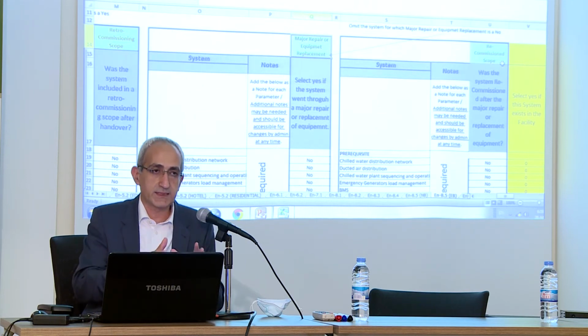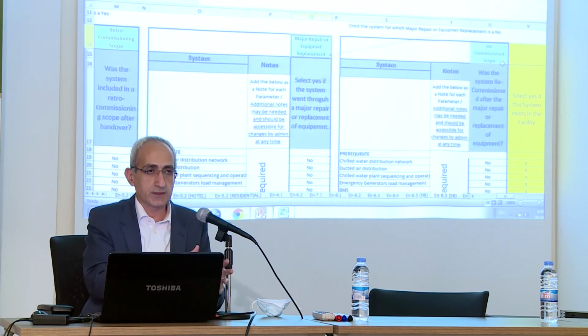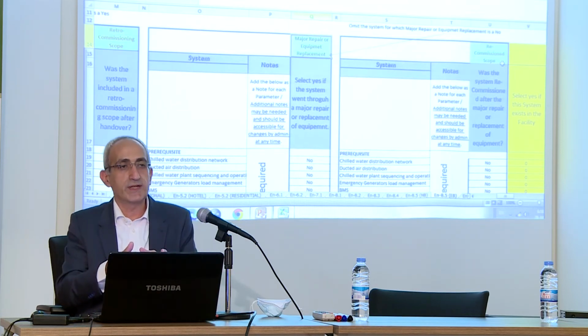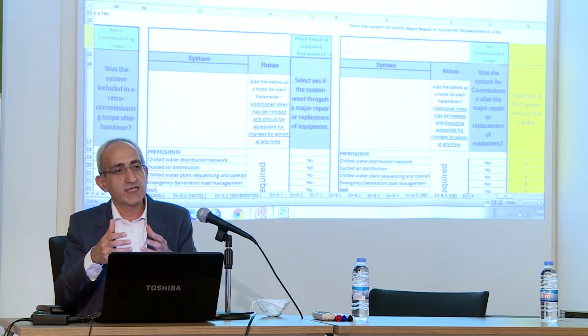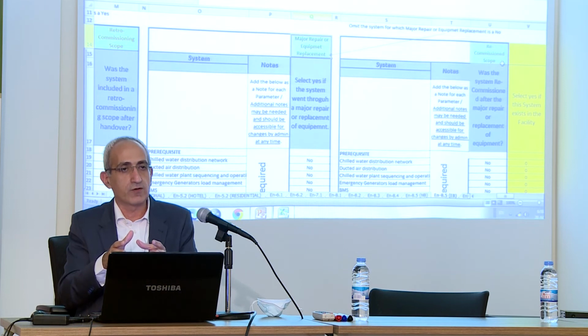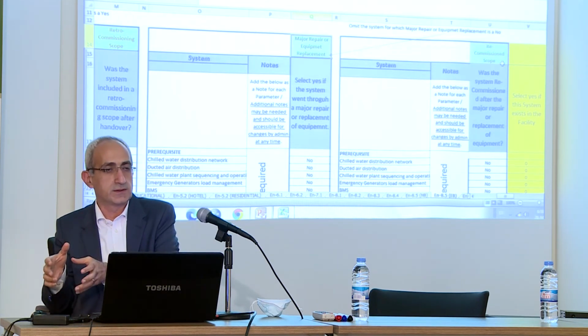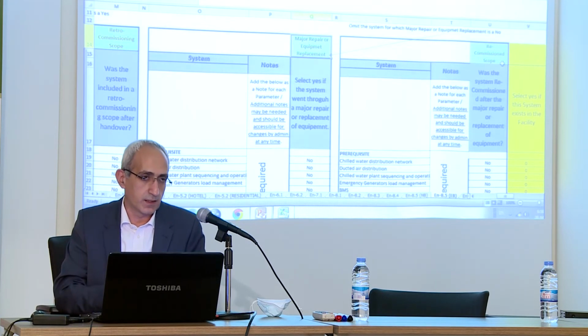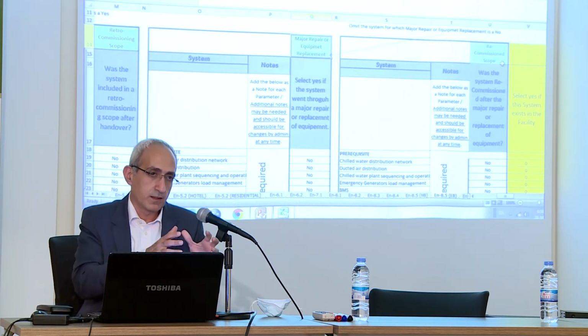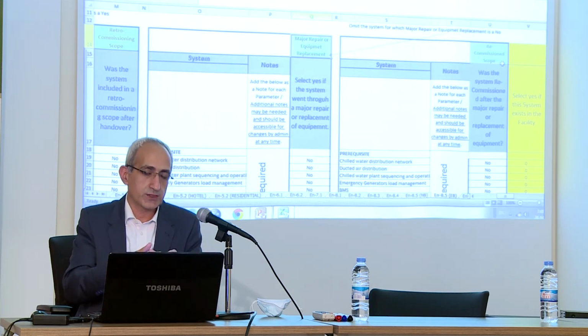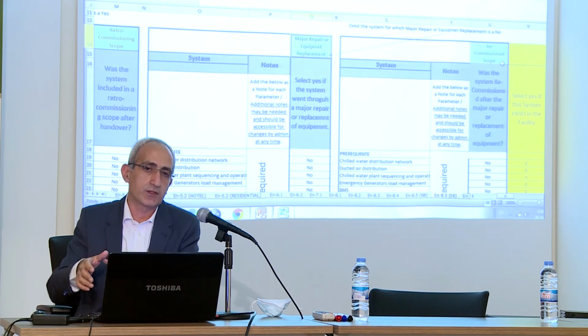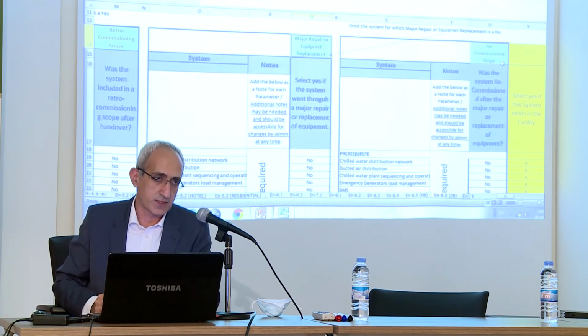So for existing buildings: if the system was commissioned initially and did not undergo major repairs - we'll have a descriptive outline in the guide of what counts as a major repair - then it is given the score. If it was not commissioned at design, it has to be recommissioned. If it was commissioned or retro-commissioned but major repairs occurred, then we have to recommission the system.